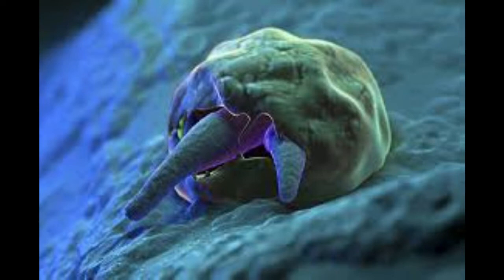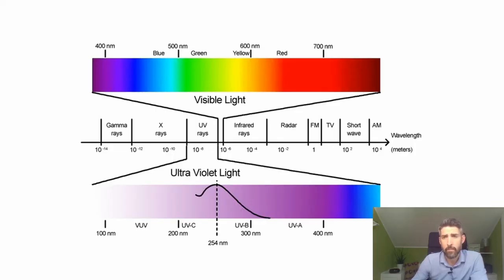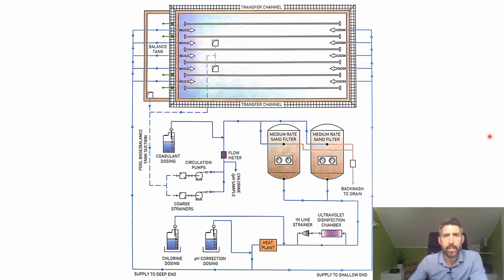It's been proven to be effective even against cryptosporidium and giardia, which chlorine isn't effective against. On a pool plant system, it's installed after filtration. The better systems will actually put 100% of the flow through the UV chamber, and then it goes through the heat exchanger and chemical dosing and returns back to the pool.